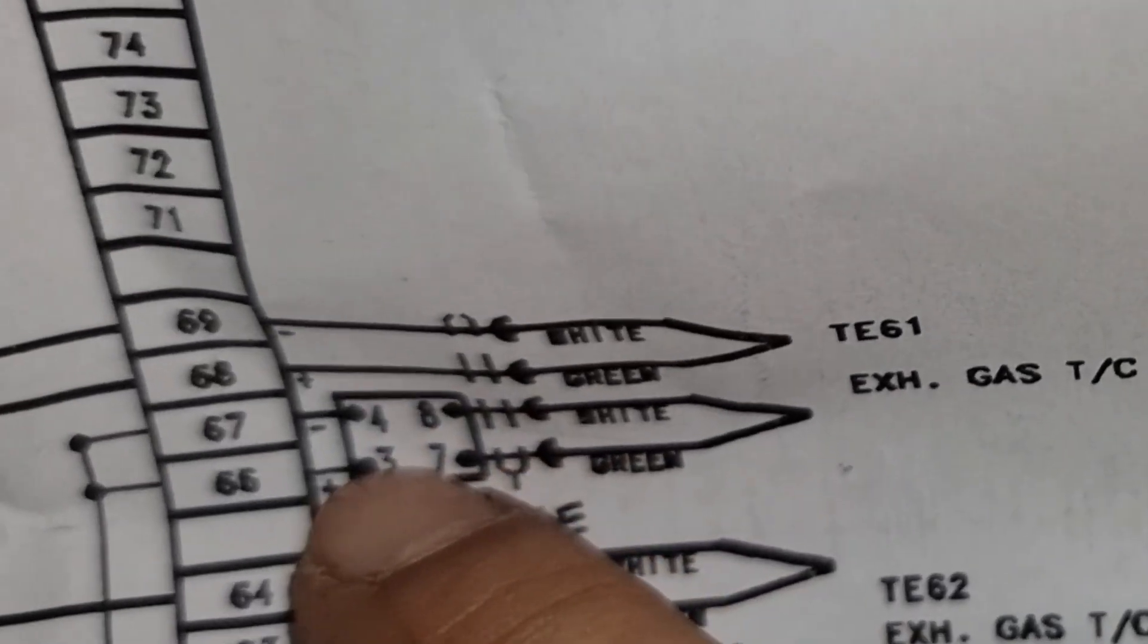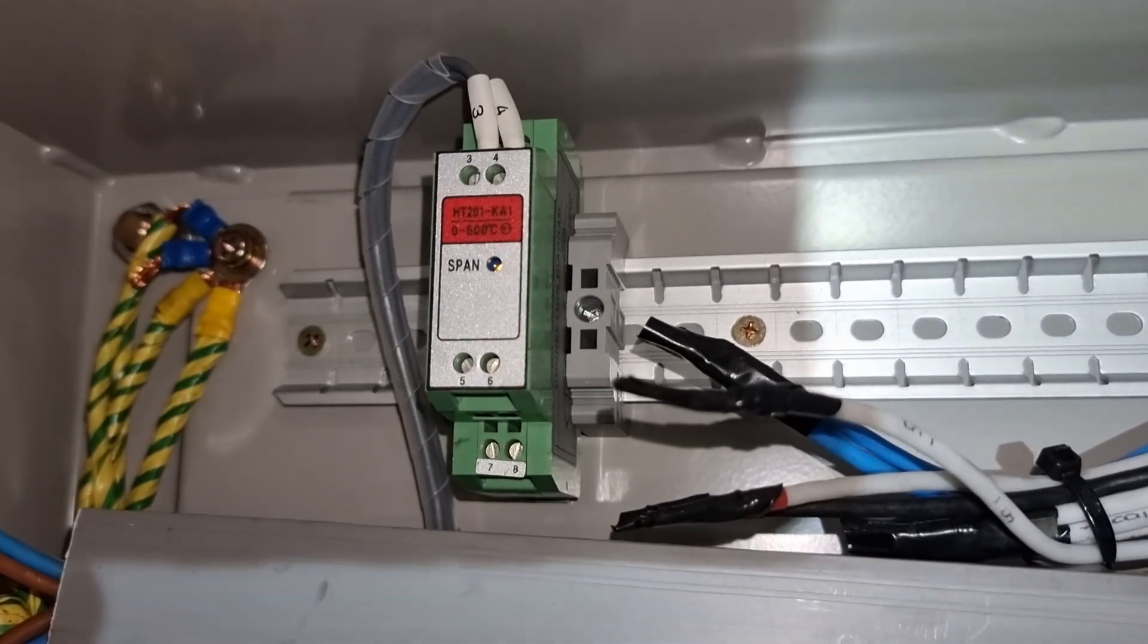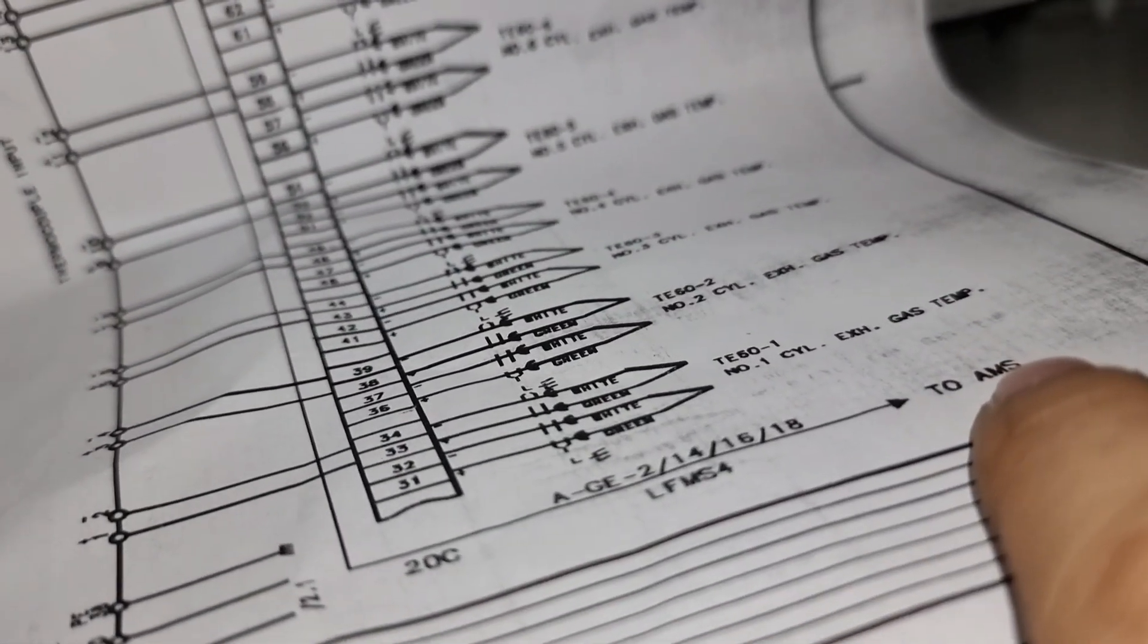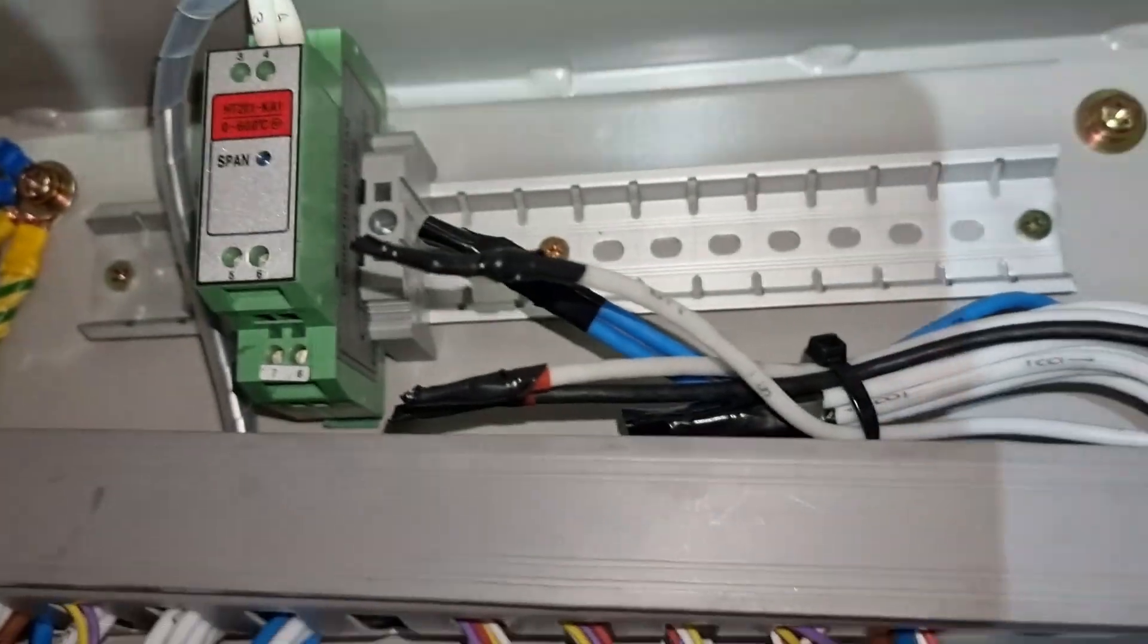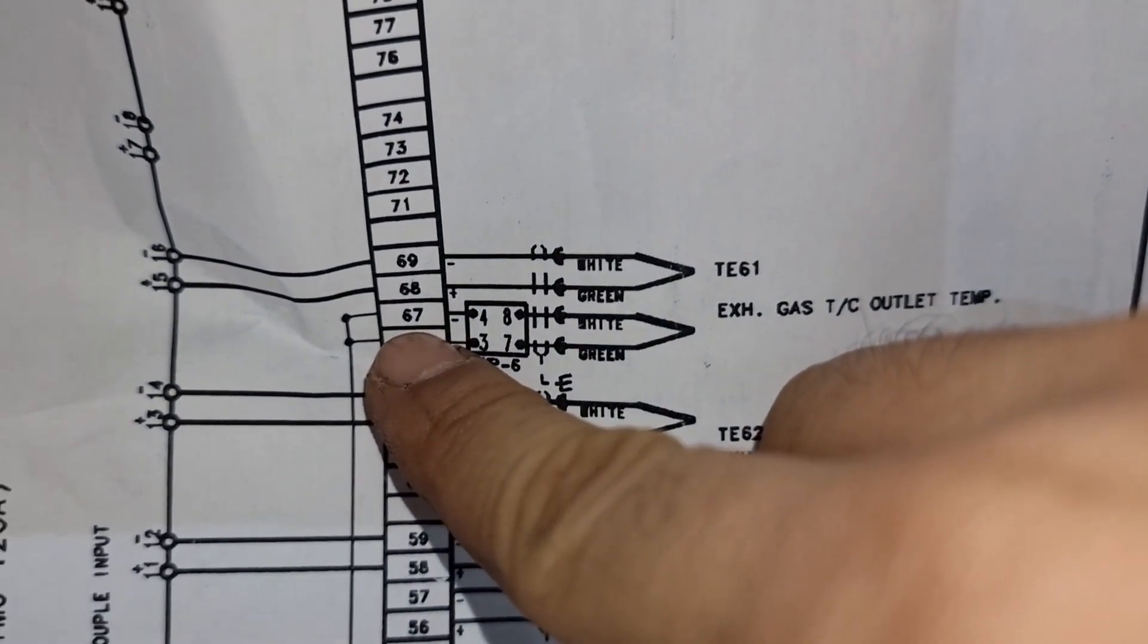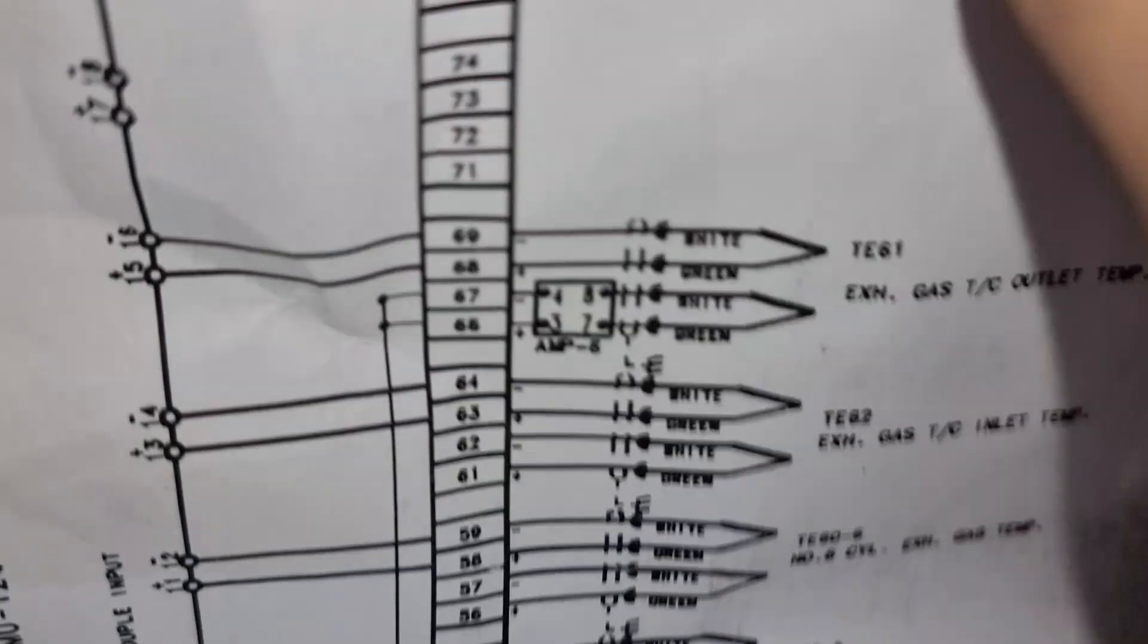The other pair should be connected to terminal 7 and 8 of the amplifier and the number 3 and 4 should go through the alarm and monitoring system. And this is not the case here, so we need to trace where is the other pair of wire. As you may notice, the newly installed sensors do not have their own tagging. So I need to trace first the number 66 and 67 terminals.